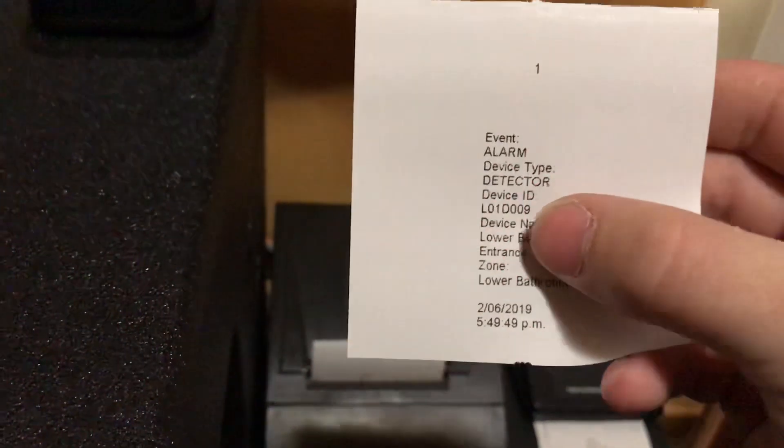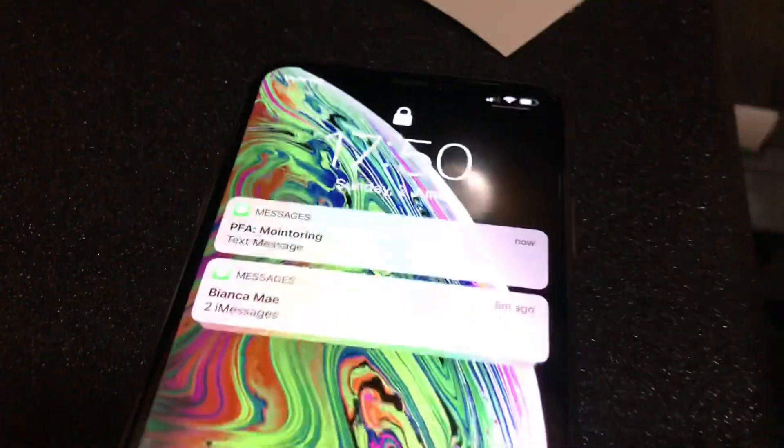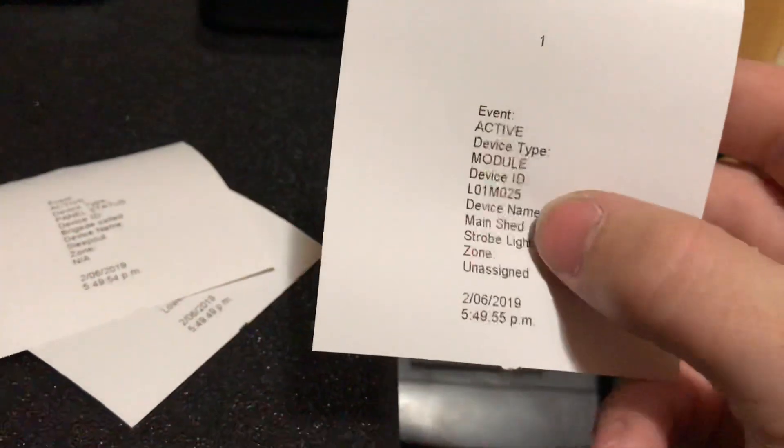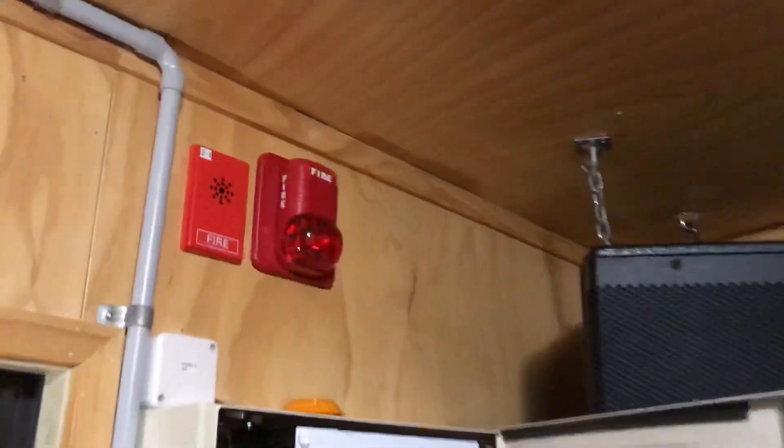Let's minimize the remote desktop client. You can see the thermal printer is printing out statuses at the moment. The first one is the alarm event, the device type is detector, the loop address which is device 9, its name — lower bathroom — the zone — lower bathroom — and the time. The second event is active: panel status and the brigade has been called. I've just got a text message through — I'll show you that in a second. The third event on the thermal printer is active, device type module, and device name main shed strobe light. If we have a look out the window you should be able to see the flashing over there — that is the strobe light in my shed. This strobe light in here is not addressable, so it's not sending a notification.